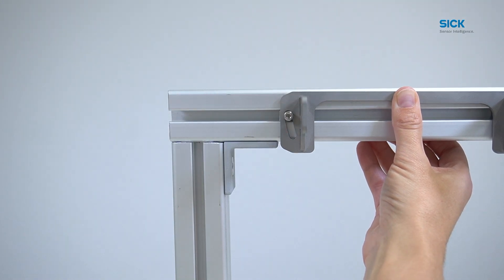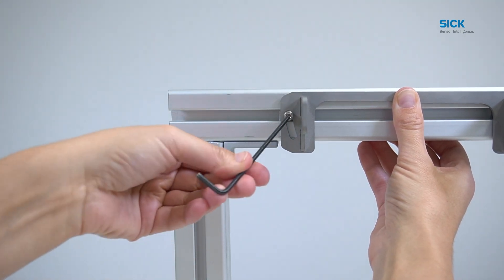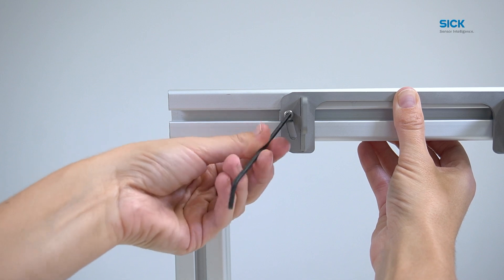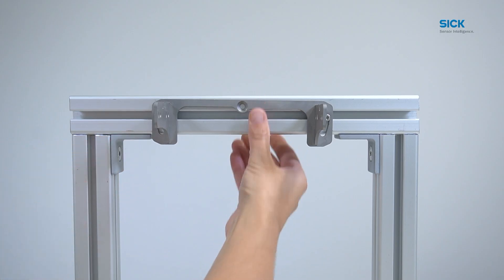Only the outer mounting holes are used for this. These holes are designed as elongated holes to adjust the horizontal mounting. The screws should therefore not be tightened tightly in this step so that the alignment can be adjusted later.